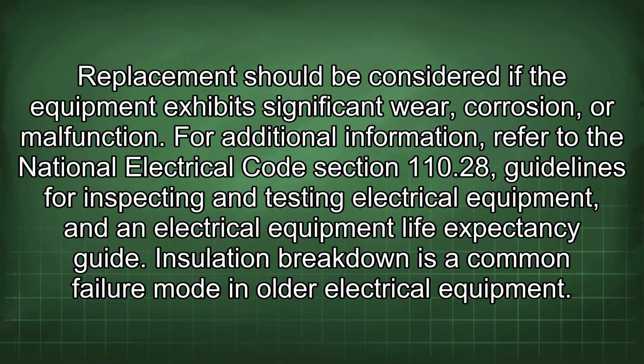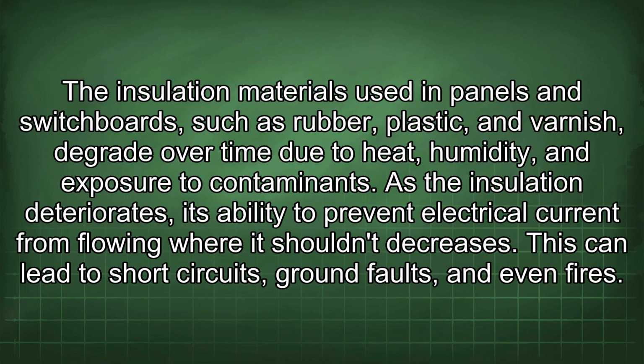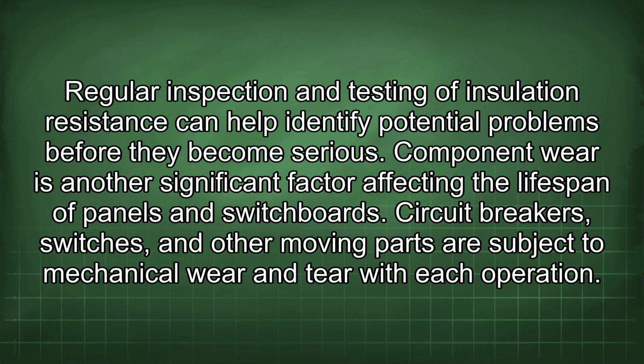Insulation breakdown is a common failure mode in older electrical equipment. The insulation materials used in panels and switchboards, such as rubber, plastic, and varnish, degrade over time due to heat, humidity, and exposure to contaminants. As the insulation deteriorates, its ability to prevent electrical current from flowing where it shouldn't decreases. This can lead to short circuits, ground faults, and even fires. Regular inspection and testing of insulation resistance can help identify potential problems before they become serious.